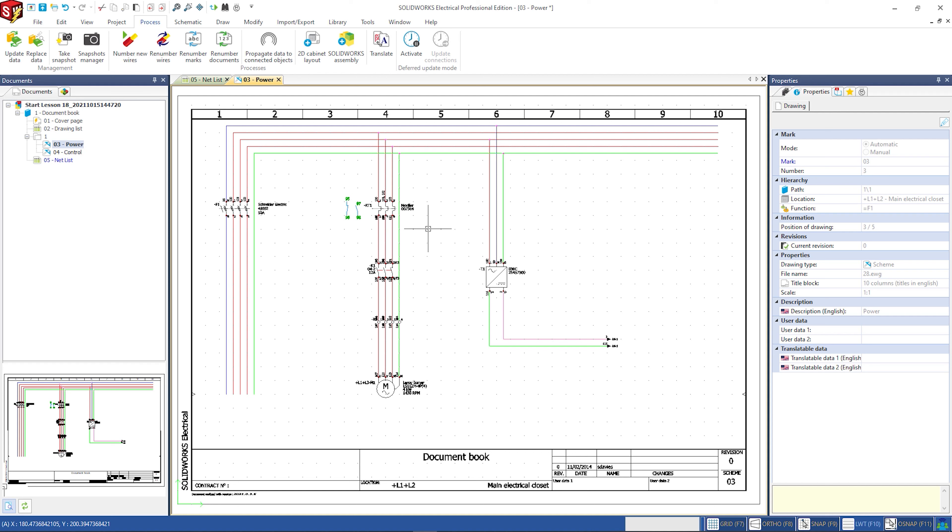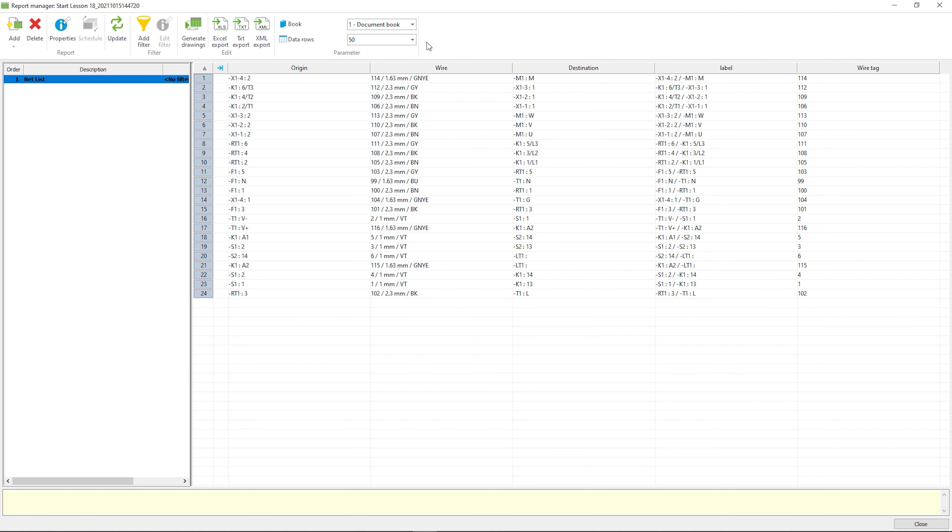In this example we are going to replace the standard wire numbers generated by the automatic formula with a label that contains the origin, destination, and component information. These labels will be taken from our wire list report.